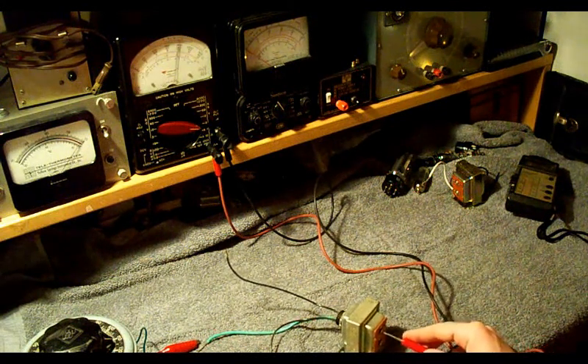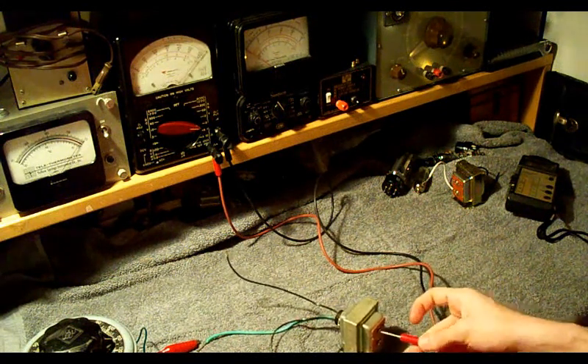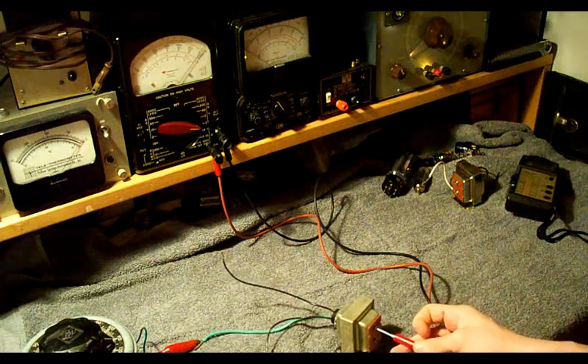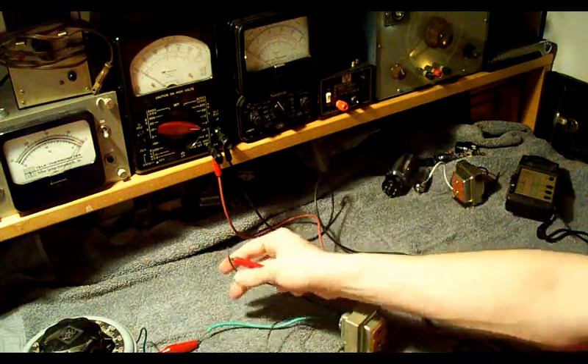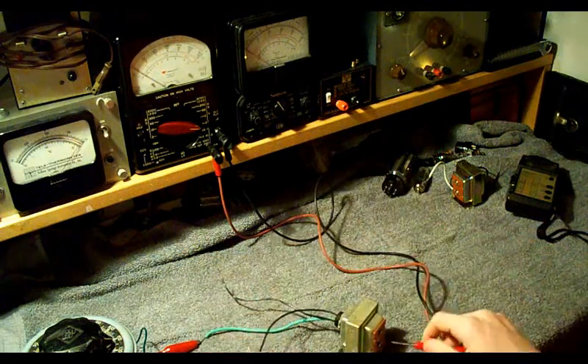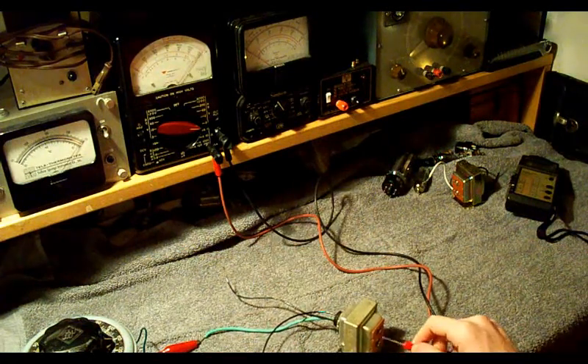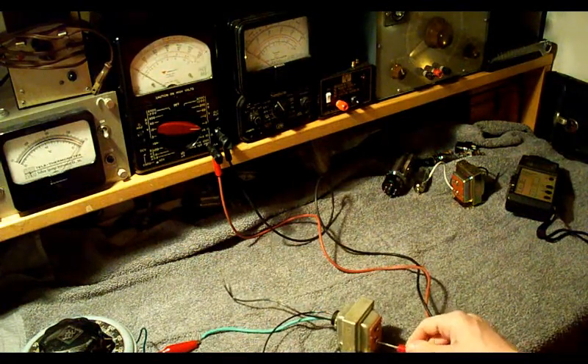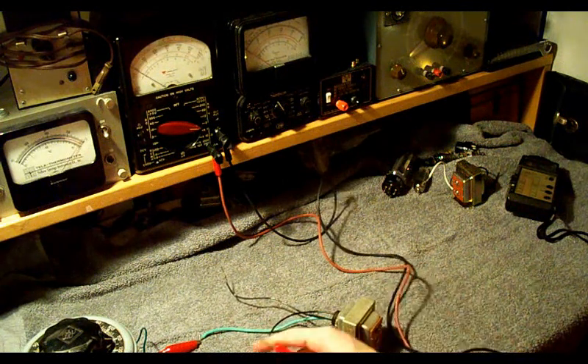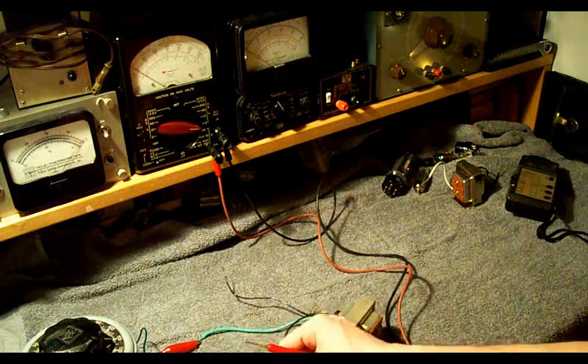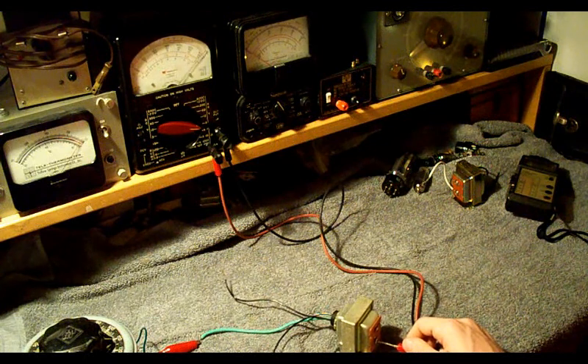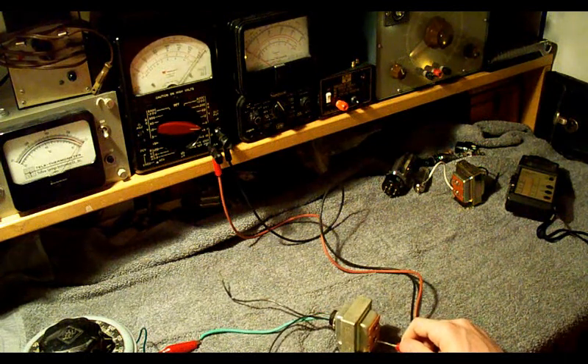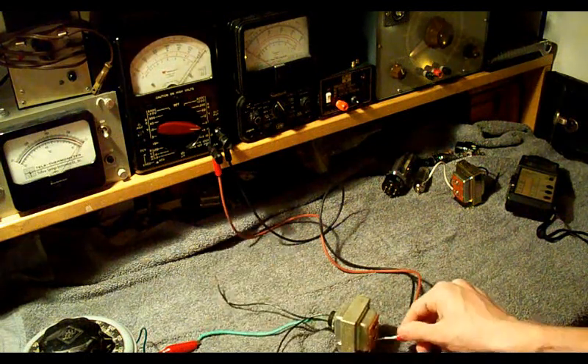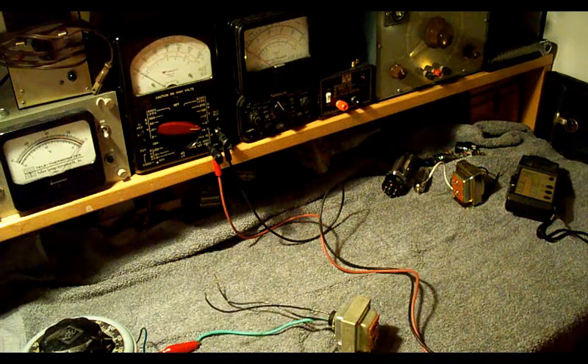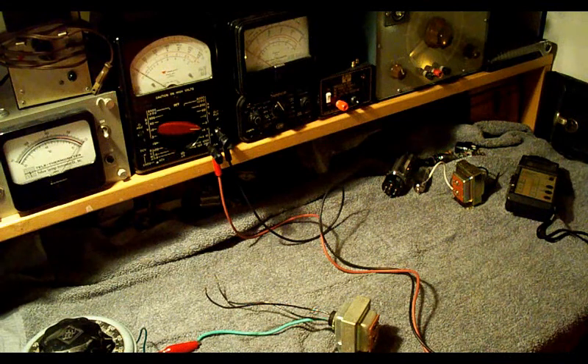Nothing to the other side of the secondary. What's this? We have 0 ohms. We have a dead short. Let's check the other side of the primary to the secondary. Dead short. So this transformer is completely shorted out inside. So something has happened to this transformer to cause us to have a dead short between one side of the primary and one side of the secondary winding. So inside this transformer, the primary is somehow making contact with the secondary.